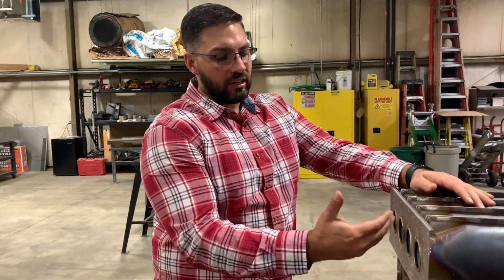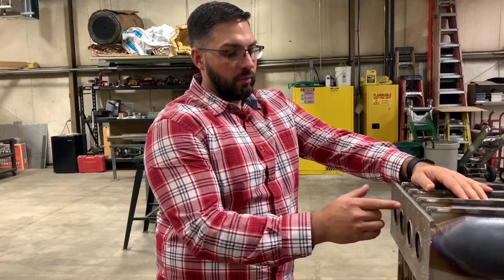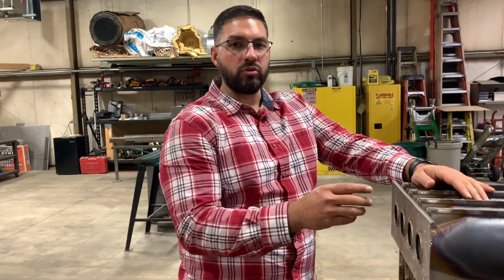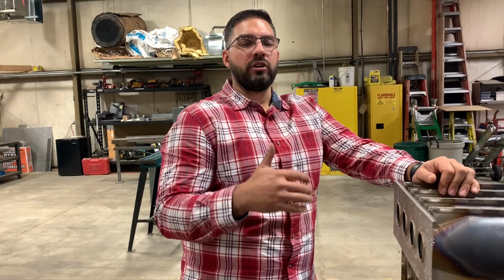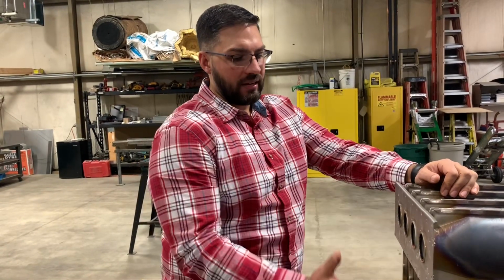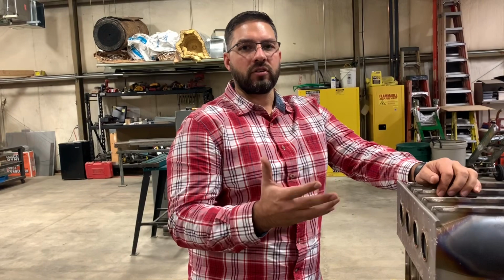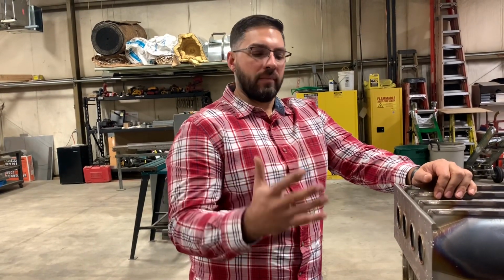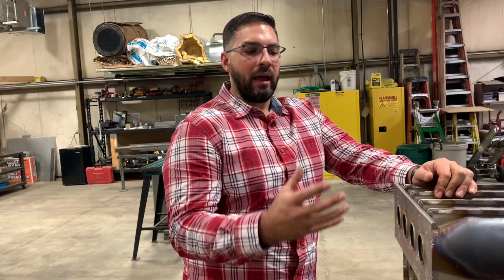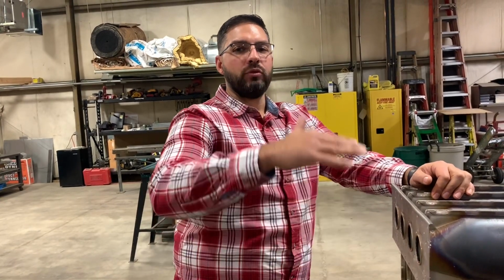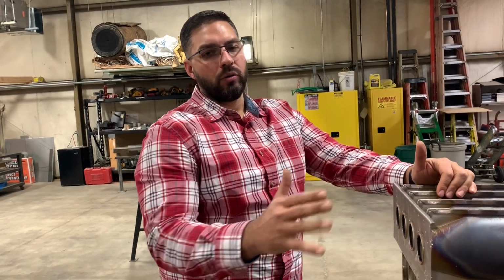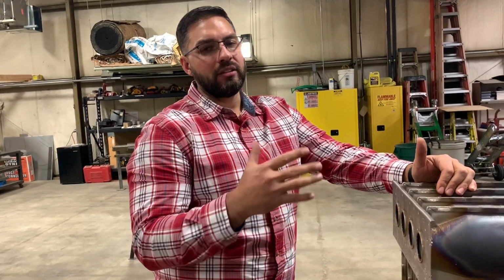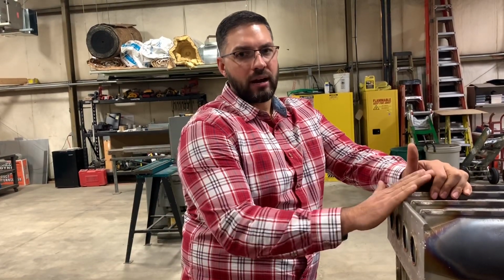What we do here at A Plus is we actually have a manometer, and that manometer goes inside. There's a limit on these things, like a heat limit, and we'll pull that limit out and stick the hose into the area, then turn the fan on to the furnace. We don't have to have the heat running, we're just looking to see if there's a crack in the heat exchanger. The manometer starts off at 0, and once that fan comes on, if it moves up from 0, that tells us immediately there's a crack in the heat exchanger. We can show it to the customer while they're in the basement so they can see it firsthand, instead of guessing and saying, oh my goodness, I don't know if there's a crack or not. They're going to have peace of mind knowing for certain whether their heat exchanger is cracked.